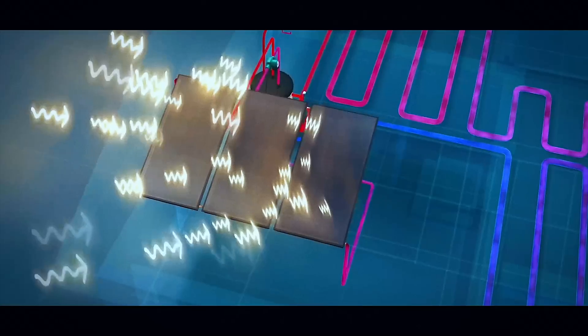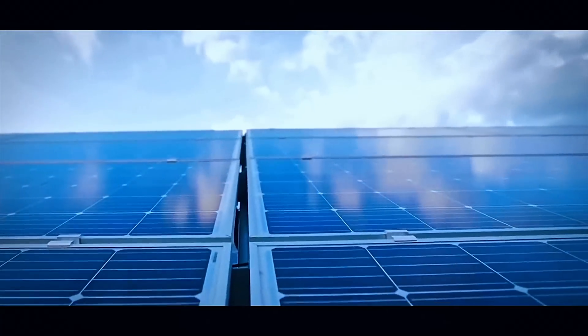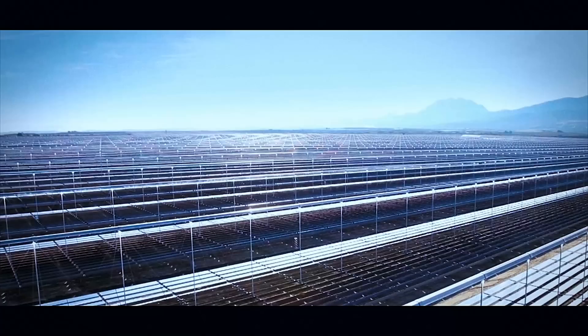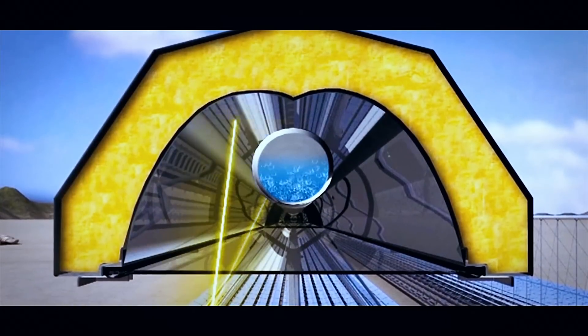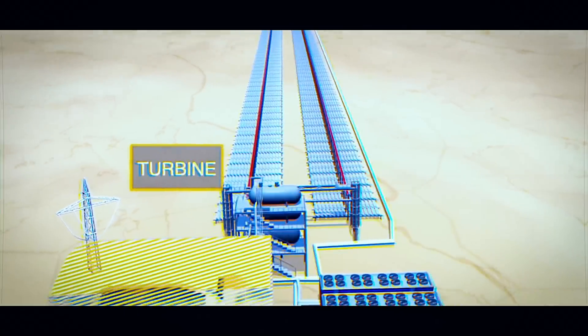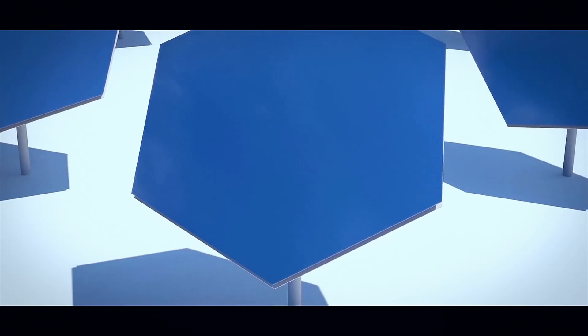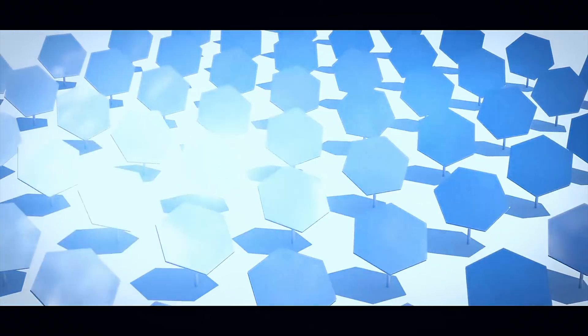Similar to wind, but in much more dramatic fashion, photovoltaic solar panel power without external storage is only usable on sunny days for a limited number of hours. Problematically, the peak generation often occurs during off-peak usage periods, meaning generating capacity is sometimes wasted. Alternate solar technologies such as concentrated solar power, CSP, uses mirrors to superheat a substance such as molten salt or oils. These pass through heat exchangers to boil water into steam, driving a turbine generator to make electricity. The hot media can be stored and used after the sunlight ceases, which makes it more convenient and useful. Still, a few cloudy days could put a real damper on that storage system. But even cold doesn't slow it down on clear days.